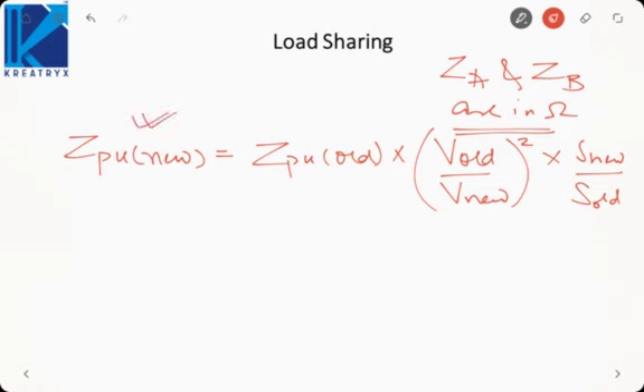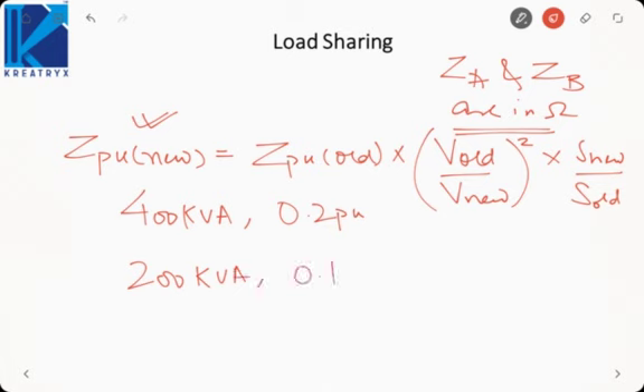Because most of the time what is given is the per unit value, but that will be on the individual base. Like if one machine rating is 400 kVA and the impedance is given as 0.2 pu. The other machine is 200 kVA and its impedance is given as 0.1 pu. Now you have two options: either change both to ohms, or convert this 200 kVA to 400 kVA.